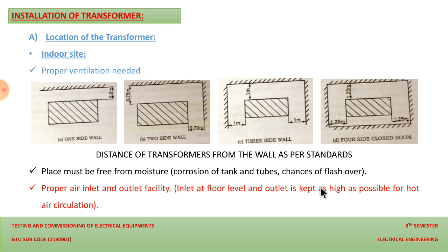The inlet is at floor level, and the outlet is kept as high as possible, because we need to release the hot flue gases or hot air for proper circulation. If the outlet is kept at a low level, then the surrounding temperature of the machine will increase. That is why we have to place the outlet, where we release the hot air, at a certain height, so that we can release the hot air easily and the inner temperature will not get heated up more. Now if we want to use the transformer at an outdoor site, these are the points that we should keep in mind.